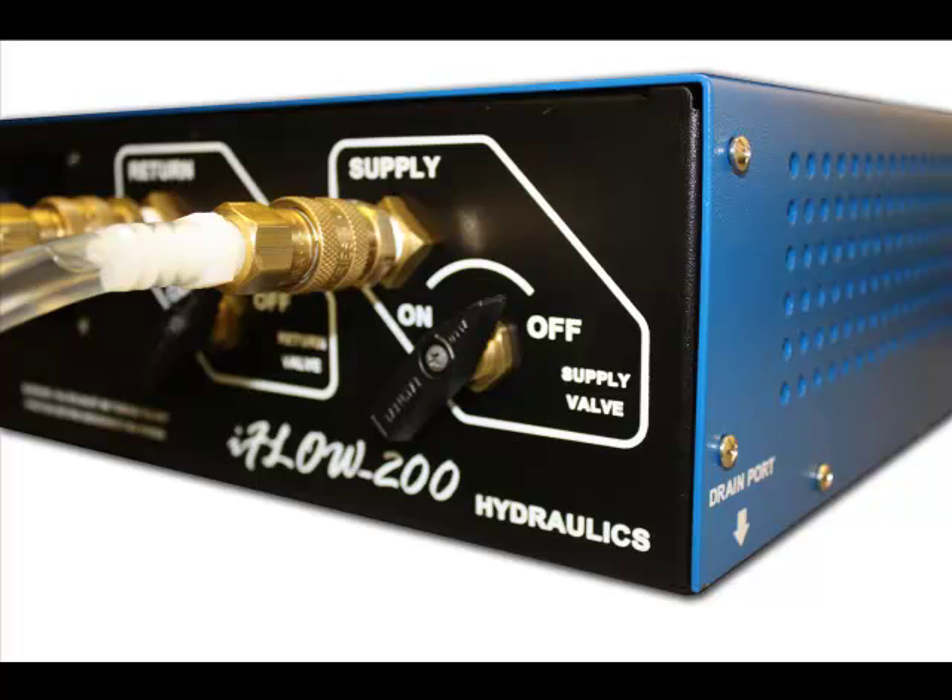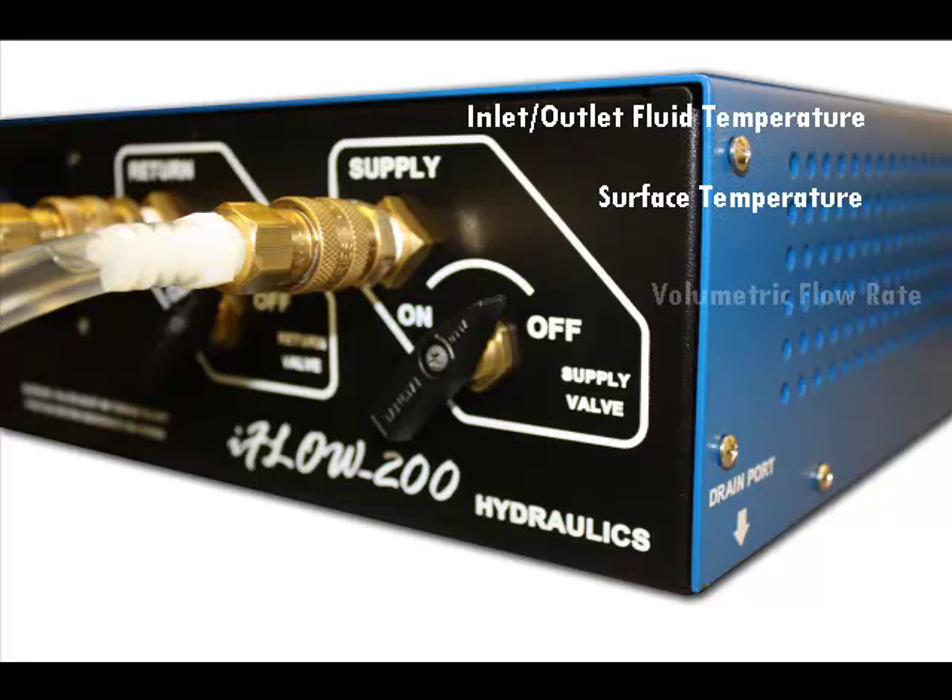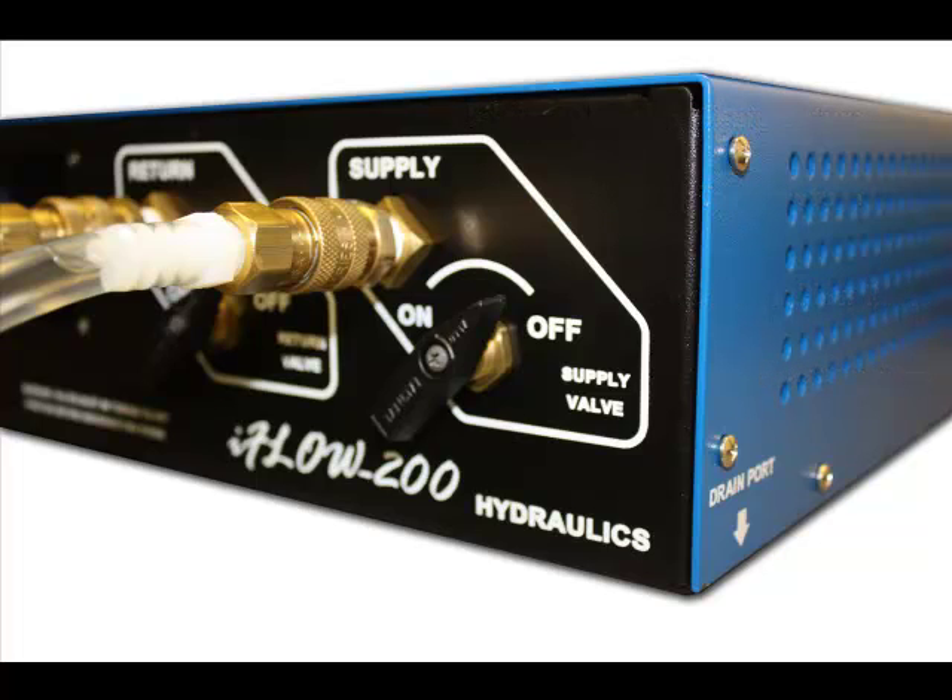The iFLOW 200 system features a separate controller and hydraulic enclosure with USB connections. This measures a cold plate's inlet and outlet fluid temperature, surface temperature, coolant volumetric flow rate, and pressure drop by providing different flow rates to the cold plate.